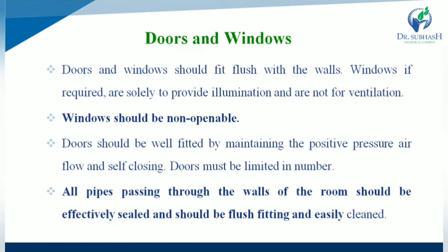Doors should be well fitted, maintaining positive pressure airflow, and self-closing, and doors must be limited in number. All the pipes passing through the wall of the room should be effectively sealed, flush fitting and easily cleaned.